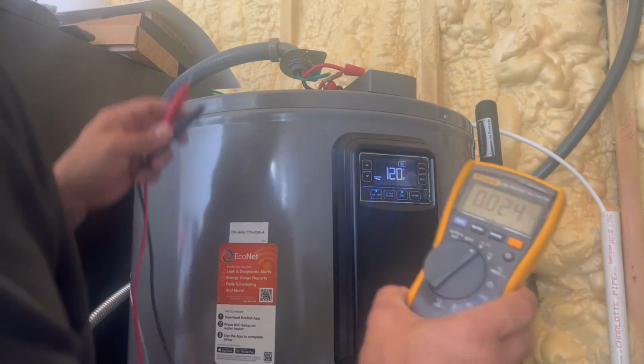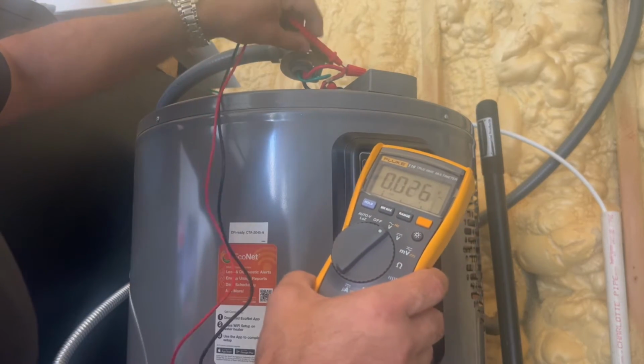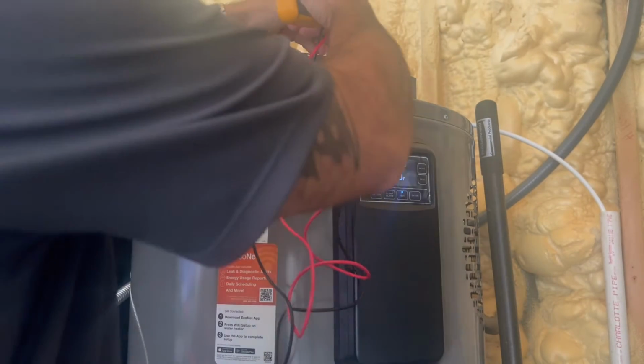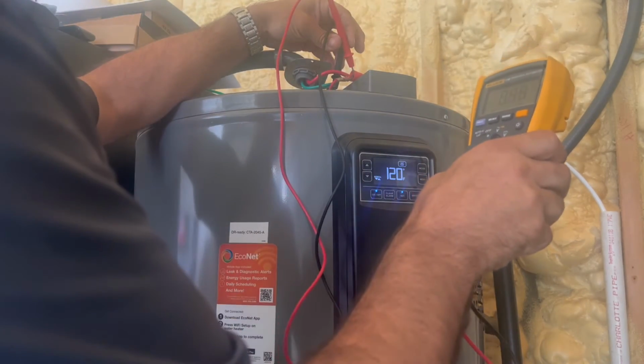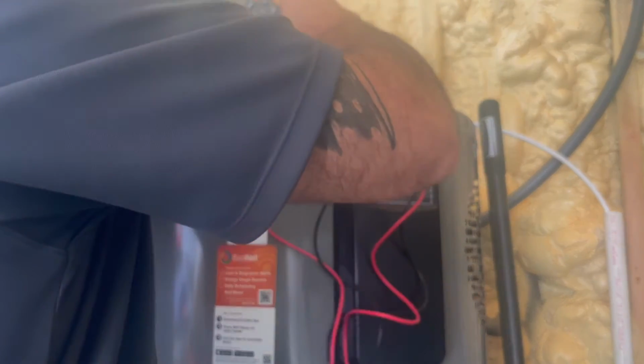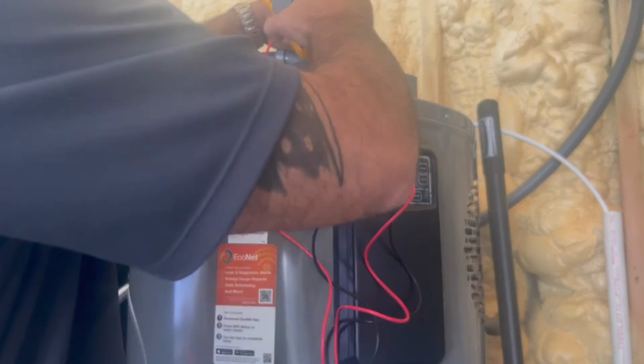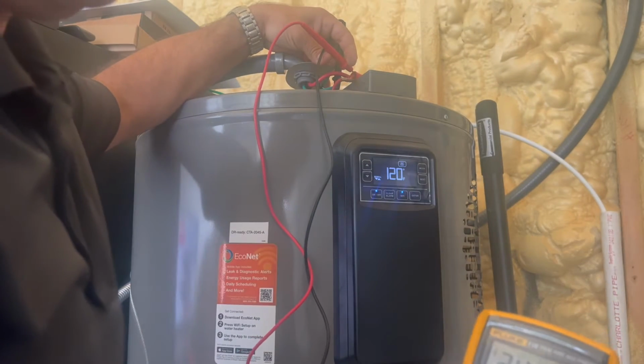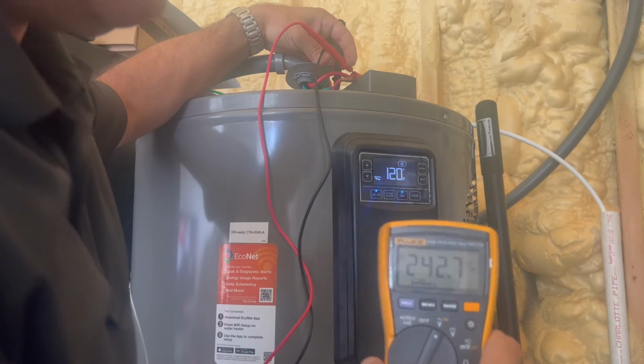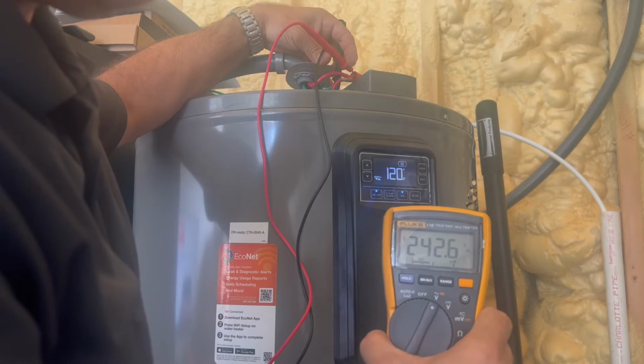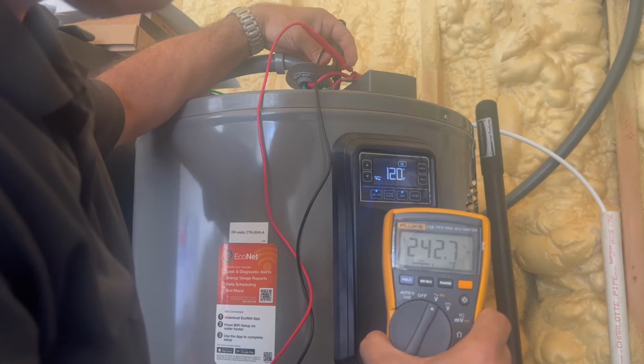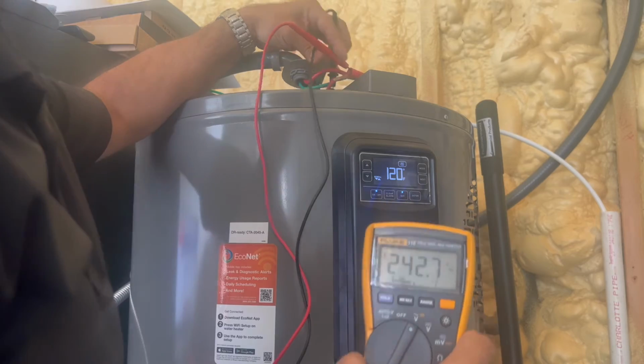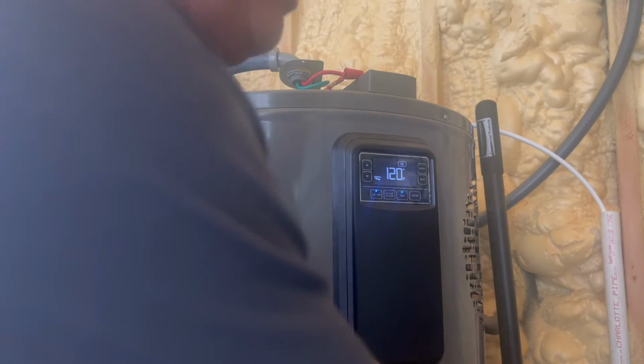All right. One probe in one side and one in the other. Let me just try and do this here with two hands. If you don't have it connected in there properly, you might get some weird numbers. So you want to try and make sure you get a good connection so you can get a good reading. 242.6. That's good. So we know we've got good voltage to the top of the heater. Now we can go ahead and put this back together.